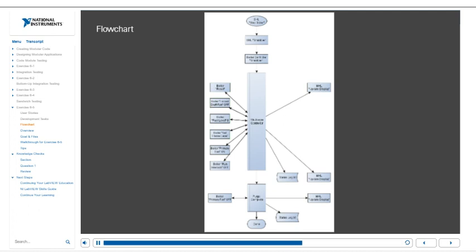Once the flame level reaches 0, the boiler controller sends messages to the boiler to turn on the primary fan and turn off the run interlock. The boiler controller then writes an update to the status log and updates the user interface. The primary fan runs for 2 seconds and then the boiler controller enters the Purge Complete phase. During the Purge Complete phase, the boiler controller sends a message to the boiler to turn off the primary fan. Once the boiler responds that the primary fan is off, the boiler controller updates the user interface and writes an update to the status log.